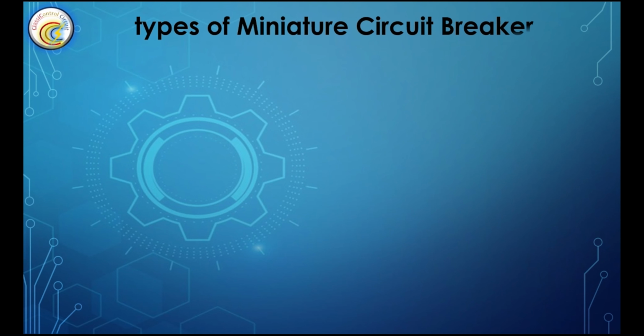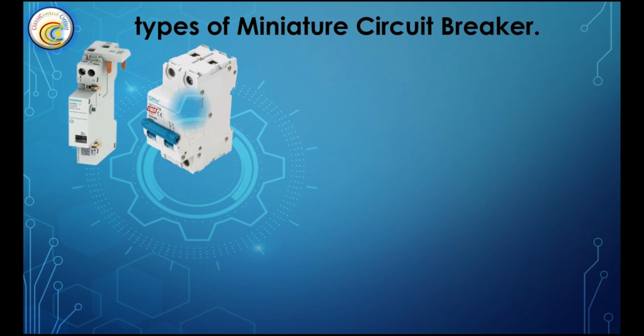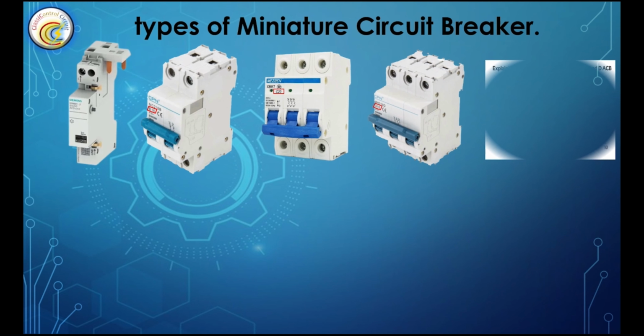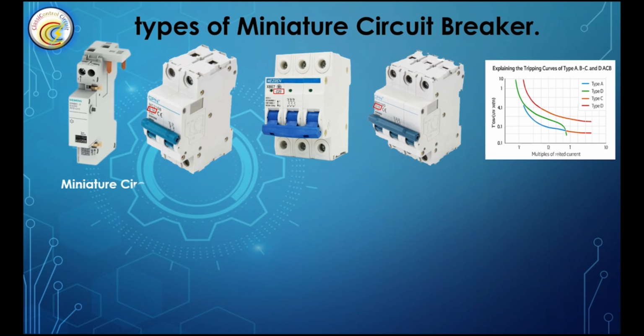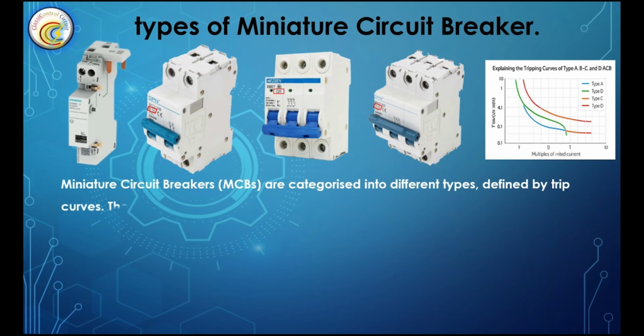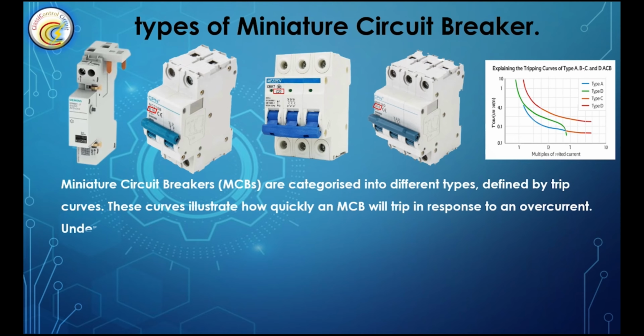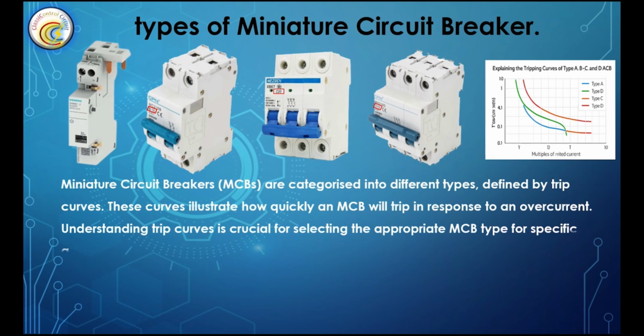Types of miniature circuit breaker. Miniature circuit breakers are categorized into different types, defined by trip curves. These curves illustrate how quickly an MCB will trip in response to an overcurrent. Understanding trip curves is crucial for selecting the appropriate MCB type for specific applications. Each type has a unique curve that dictates its sensitivity to overcurrents, ensuring that the MCB provides optimal protection without unnecessary tripping.